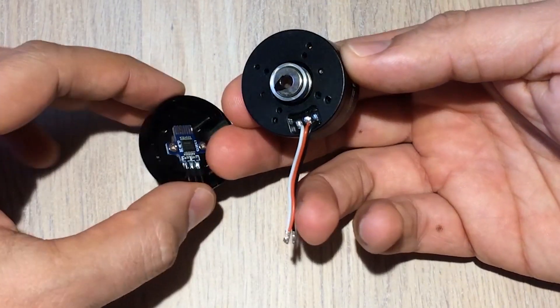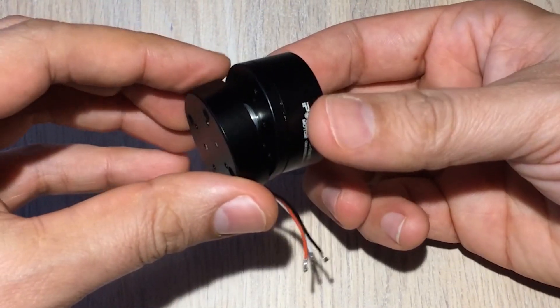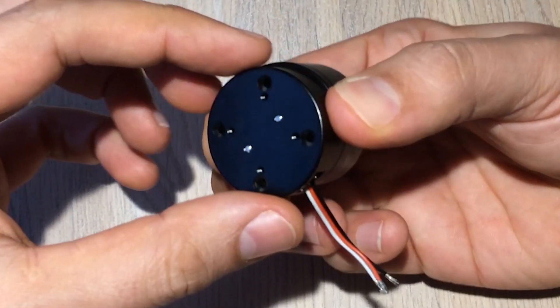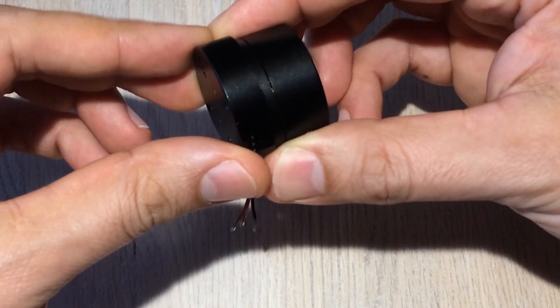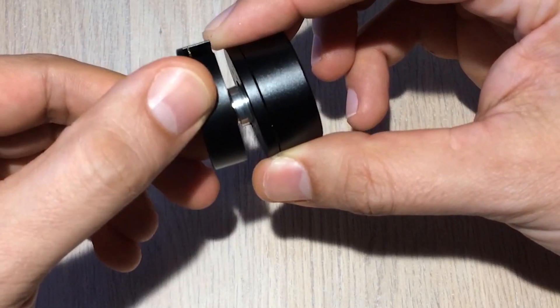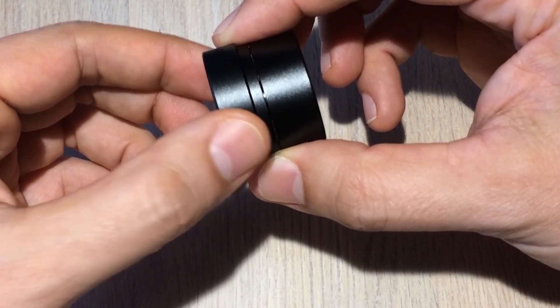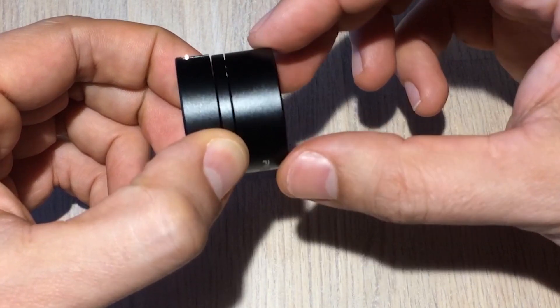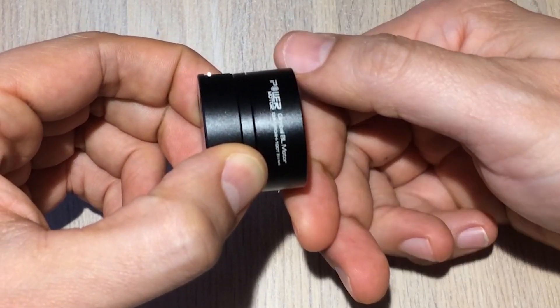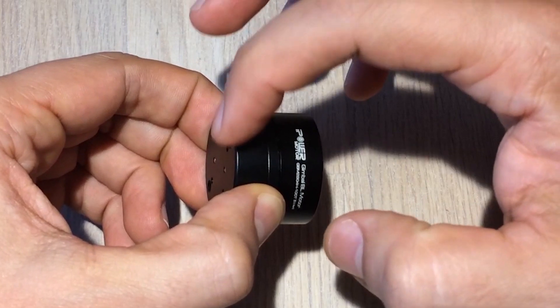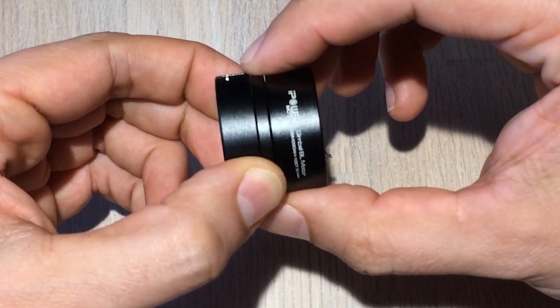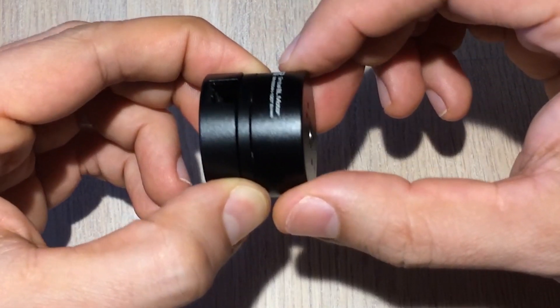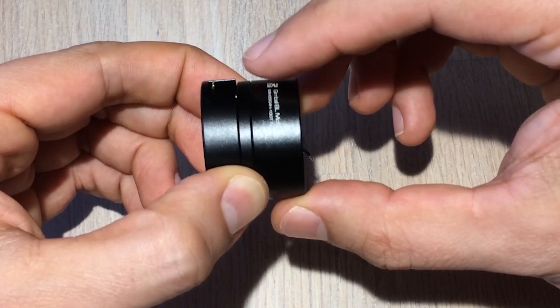Another thing is that when we put the sensor on top of this, we might assemble it like this, but we could also be assembled 90 degrees apart or 180 degrees apart. This will create an offset between the magnet fields inside the motor and the sensed position by the encoder. So the next thing we need to do is synchronize those two.